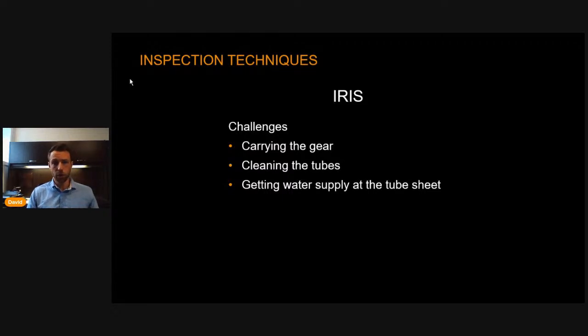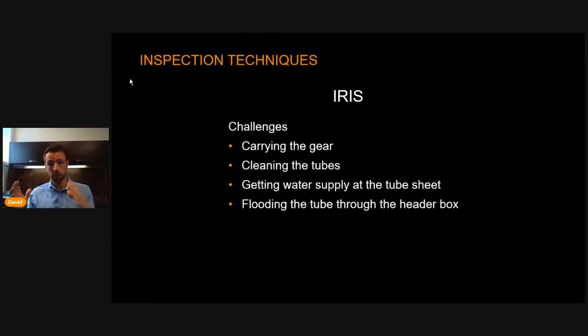Then to flood the tubes, you need to get the water, so it might be quite a challenge in itself, bringing the water all the way up to the catwalk, flooding the tube through the header box. Remember this space - imagine if you're trying to make sure your tube is flooded at the same time, but you don't have access to it directly. It can be an added challenge.